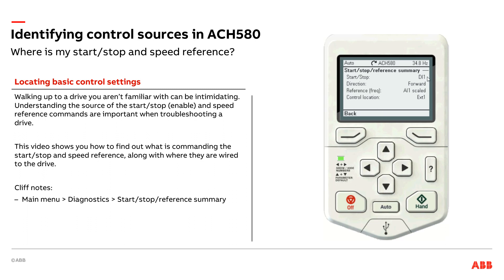My start/stop is landed on Digital Input 1, and my speed reference is set up as an analog input reference on AI1. Had I been getting a signal over the embedded fieldbus like BACnet, or if my start/stop was over BACnet, I'd be able to see that here. But in this case, it's hardwired — Digital Input 1 for my start/stop, Analog Input 1 for my speed reference. Those also happen to be factory defaults.